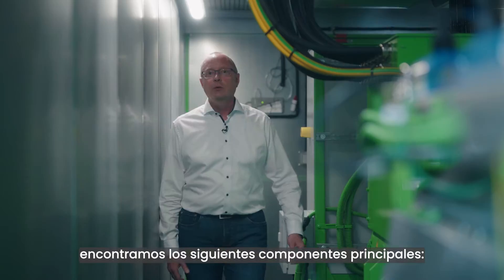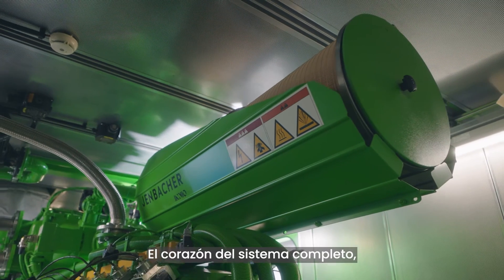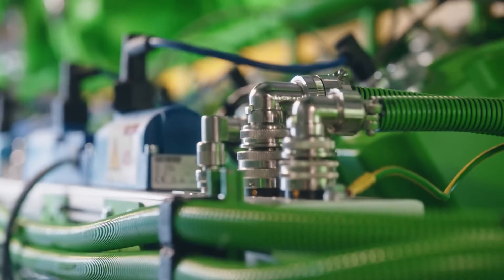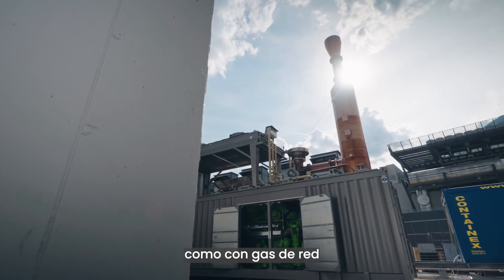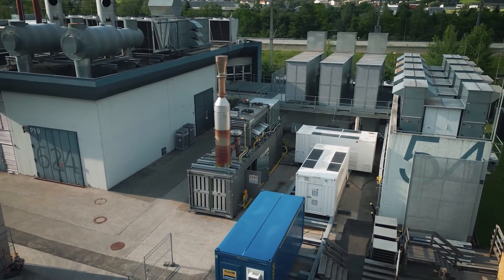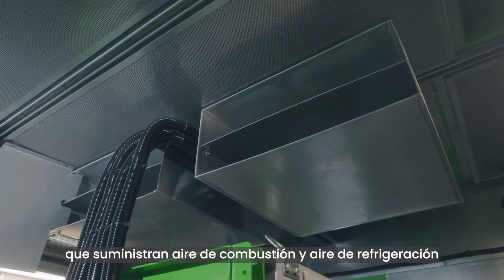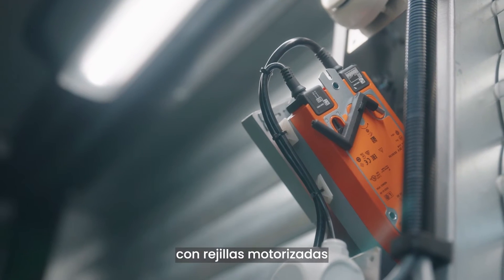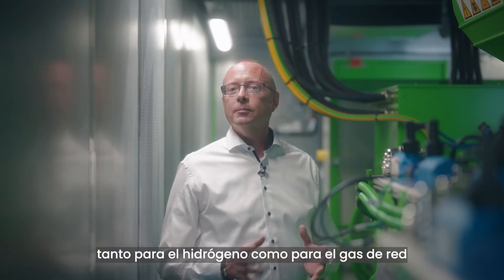Moving on to the engine room, we can find the following main components. The heart of the complete system is the Jenbacher 420 genset. This dual gas genset can operate on both hydrogen and pipeline gas and has an electrical output of 1 megawatt in hydrogen operation. The air inlet ducts provide combustion air and cooling air. The gas train for the pipeline gas, the air outlet sound attenuation with motorized louvers, as well as smoke detectors and gas detectors for both hydrogen and pipeline gas.